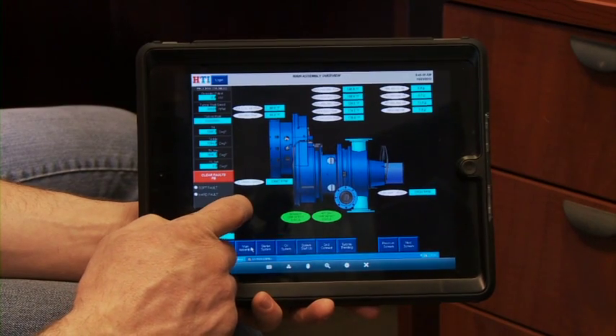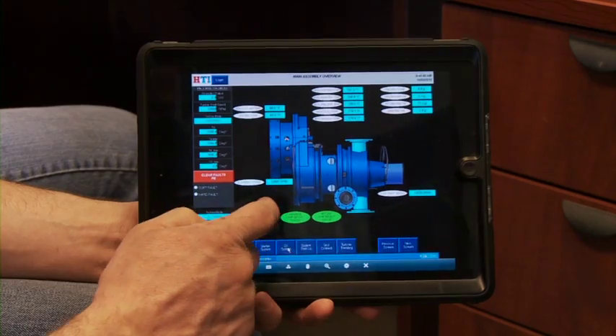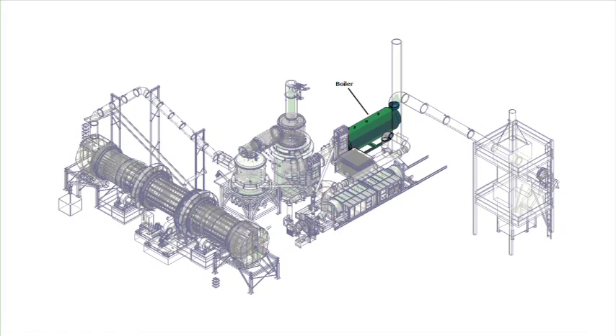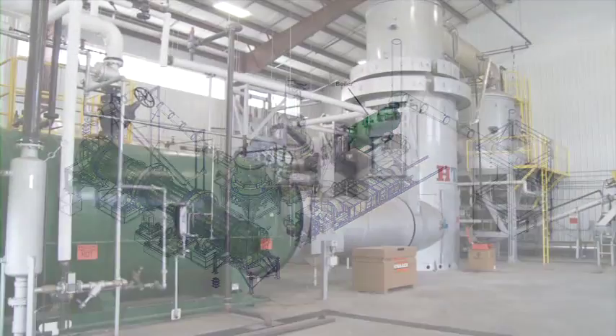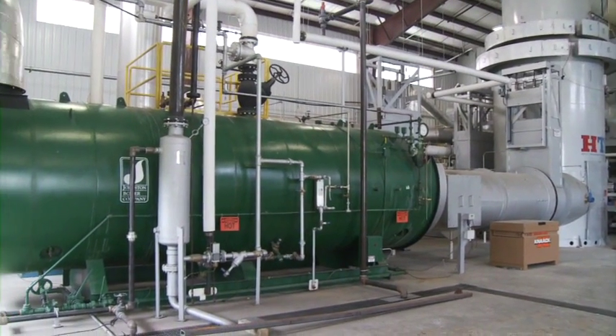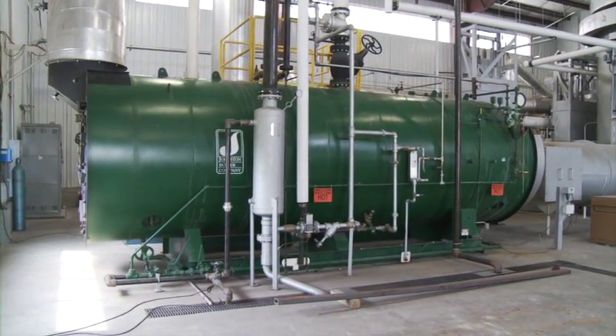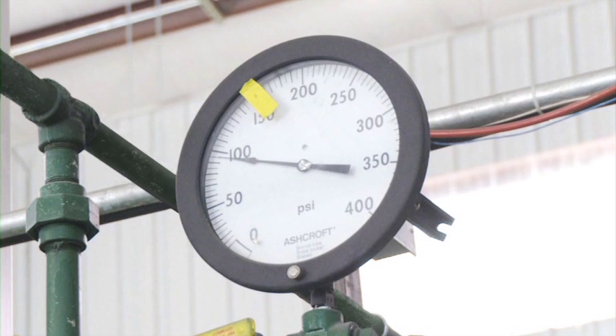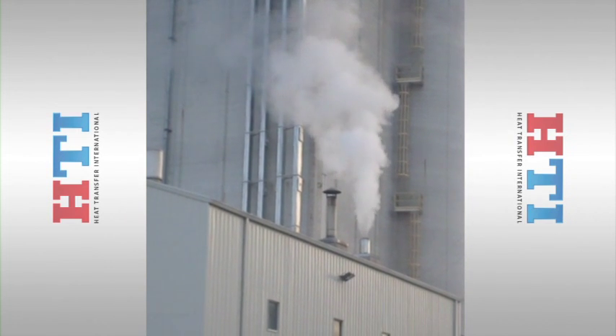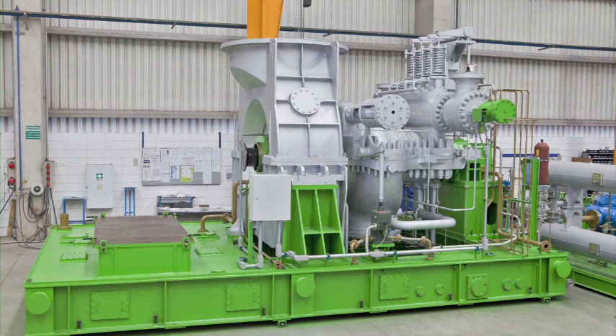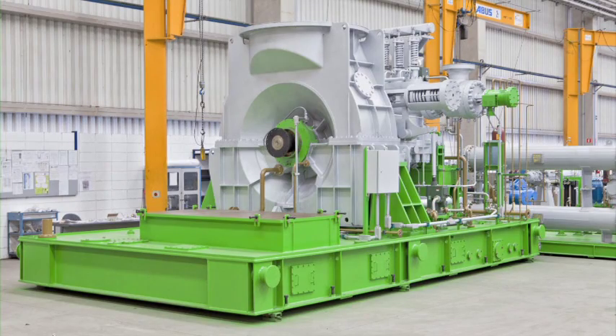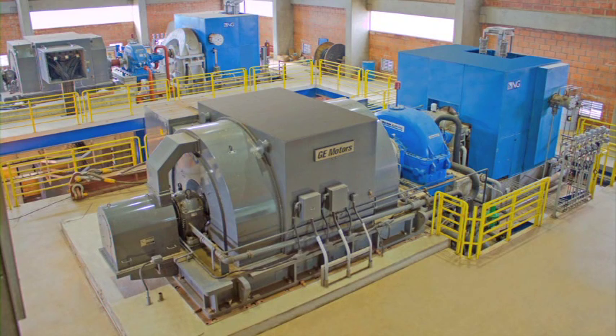After the turbine has used the energy it needs to make electricity, the excess hot air is sent to the boiler. The gas leaving the turbine is now back to 1000 degrees Fahrenheit and enters the boiler, where additional energy is captured through the creation of steam. On larger systems, a steam turbine is the preferred option for energy production.